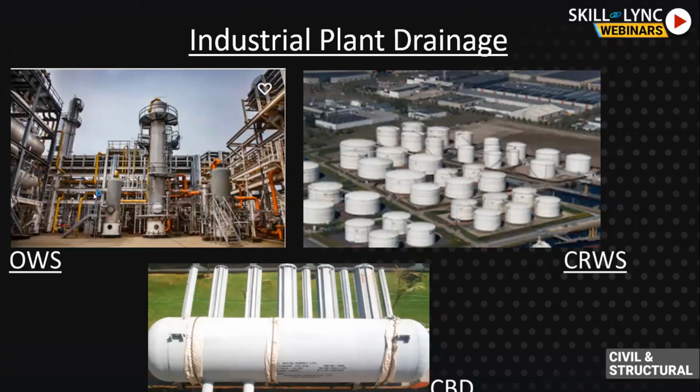Okay, so you should know the chemical engineer and the piping engineer on your project. He will help you to estimate the discharge going into your pipe. You have to design this downtake, the rainwater downtake, for whatever discharge it is. As it comes down, if it is contaminated, it will not be sprayed over here. There will be a small pit or chamber over here. It will enter that chamber. From that chamber, there will be another chamber over here. Chamber to chamber, there will be underground pipes, a mesh of pipes connected, and finally it will be taken to the effluent treatment plant. So this is how the process happens.